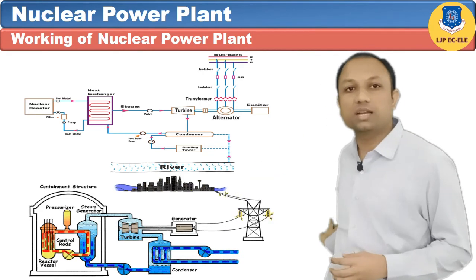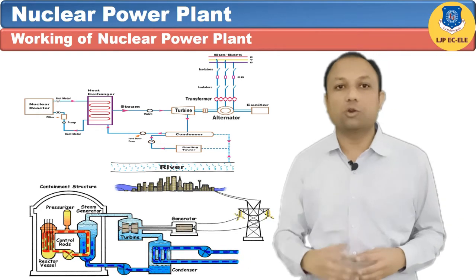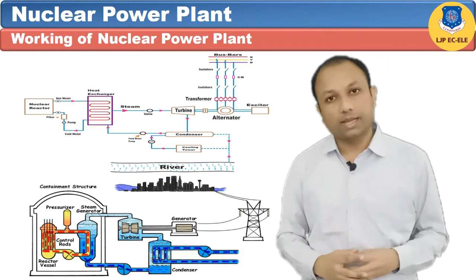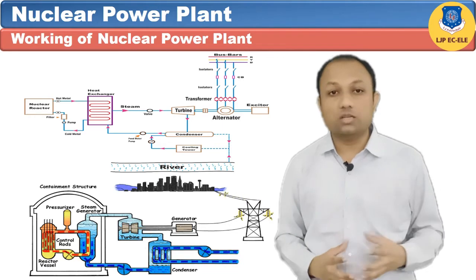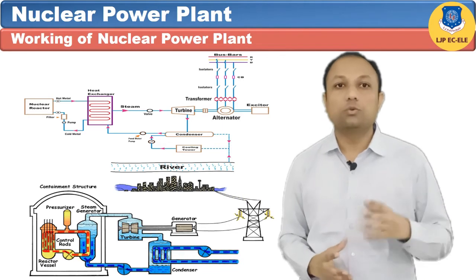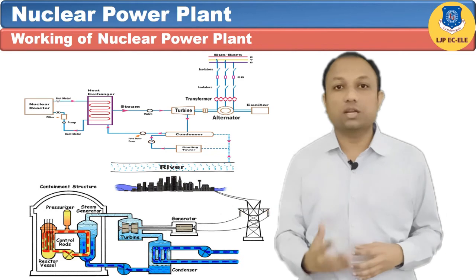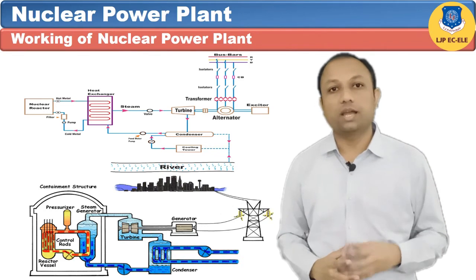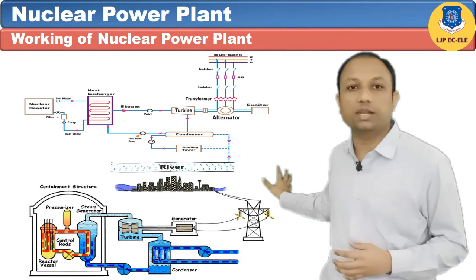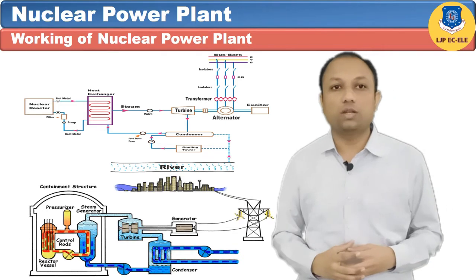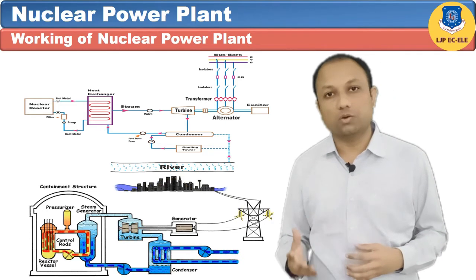When there is sufficient water in the river throughout the year, the hot water coming out of the condenser is discharged into the river and cooled by allowing it to flow through a canal. When the water in the river is not sufficient, cooling towers are used. Hot water is cooled in the cooling tower and cold water is again circulated through the condenser. In such a case, only make-up water is taken from the river or well.